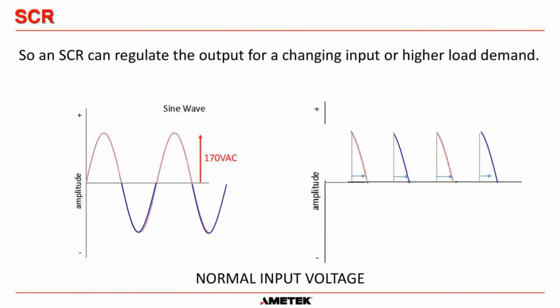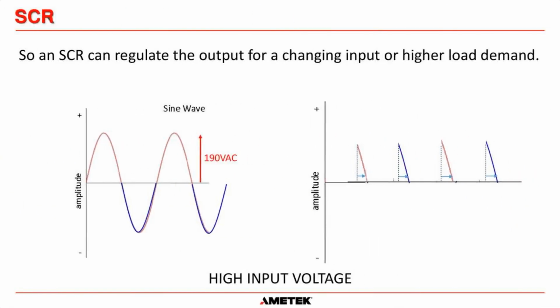If we had 120 volts input, where the peak goes up to 170 volts, we've switched the SCRs on a little later in the half cycle—not right at the top of the peak, a bit further into the waveform—but that maintains our output at 100 volts DC. We're regulating the output because we can turn those SCRs on whenever we want. And if we had really high input voltage, with the peak up to 190 volts, we'd turn the SCRs on really, really late in the cycle to maintain that 100 volts DC on the output.